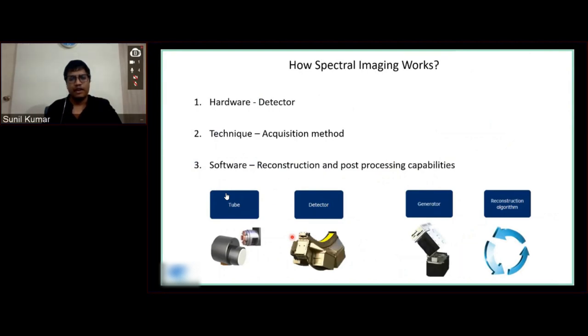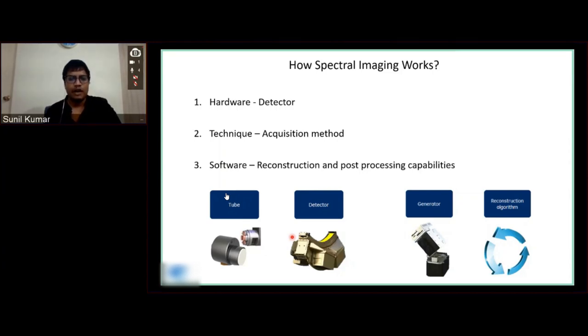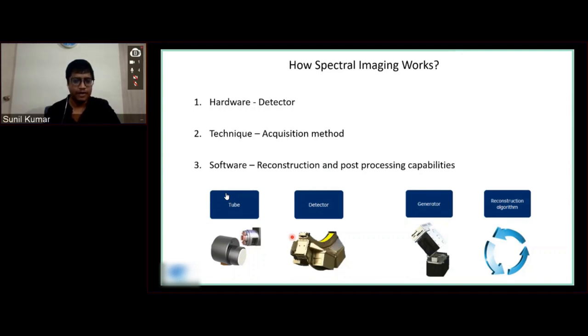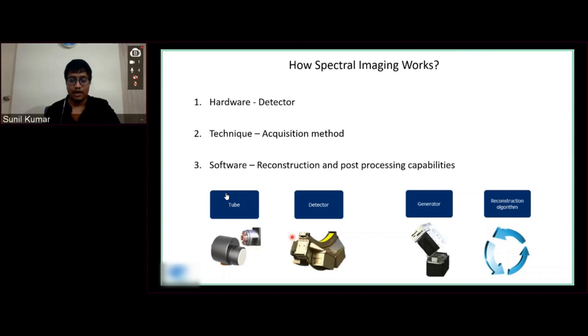So what do we need to produce a spectral image? There are three components. One is the hardware — mainly I stress on the detector, and of course we need the tube as well. And the technique, because we have different kinds of approaches to obtaining spectral CT. We also need the software, where the reconstruction and post-processing capabilities must be possible, because spectral imaging acquires data at multiple energy levels. We need our system to handle and enable us to process that.